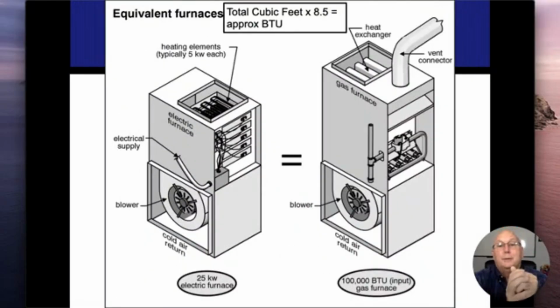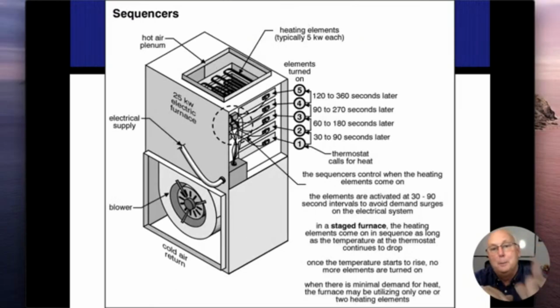So when we're talking about the difference between gas appliances, we deal with BTUs. When we deal with electric appliances, we end up dealing with kilowatts that come out of these things. There is an equation. I think it's at the very top where it talks about the difference between the kilowatts and the BTUs and the size, but we don't really get into that. We want to make sure we get enough hot air flowing and check our temperature rises. The biggest problem with electric furnaces, especially in the summer months, we have trouble getting all the elements on.